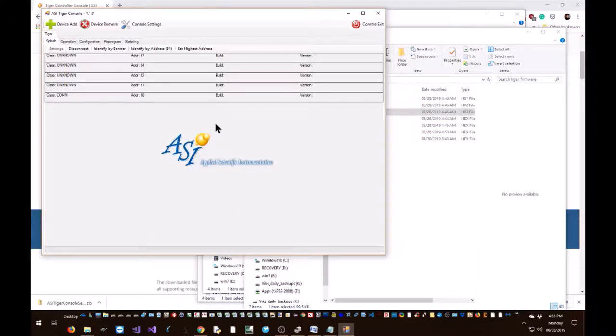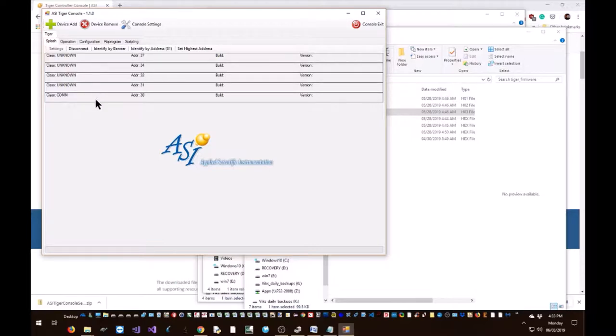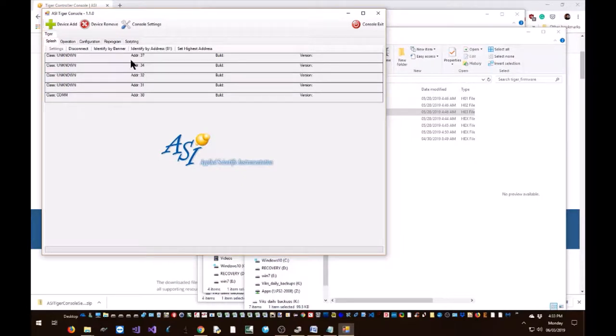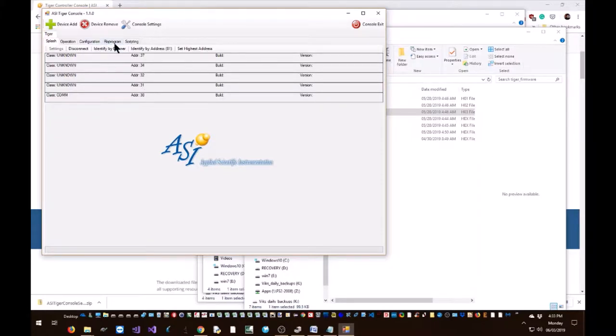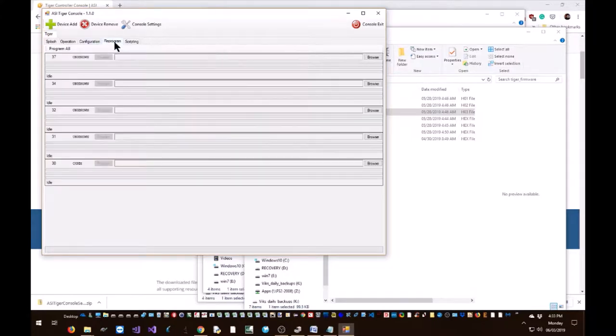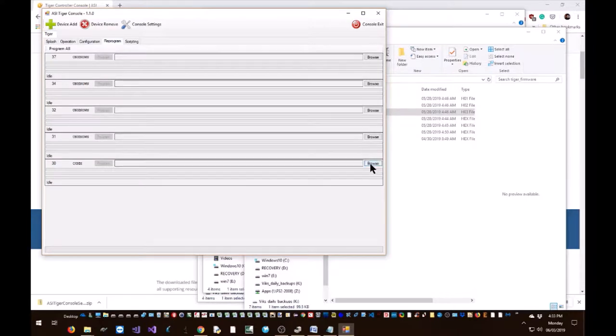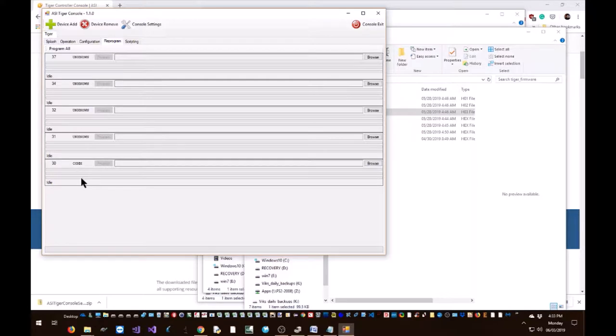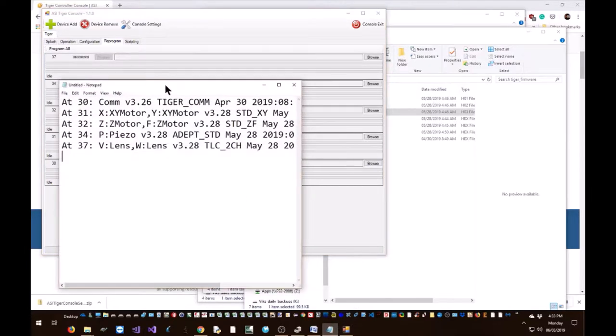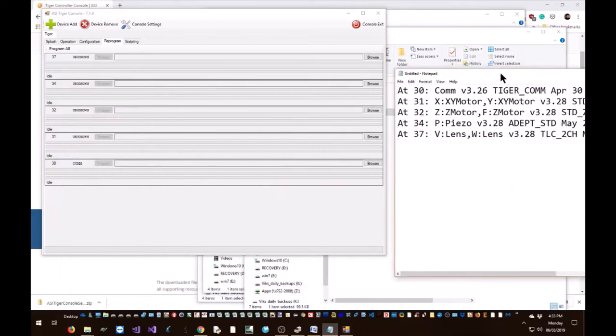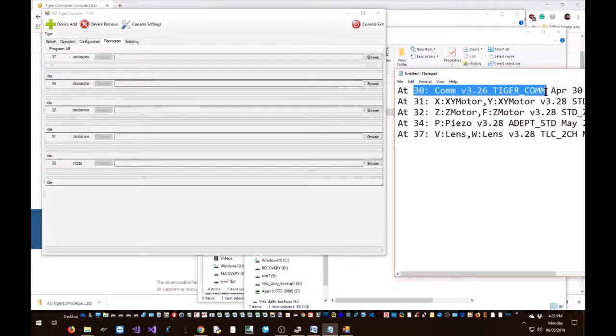Okay, now the COM card has queried all the cards that are present in the box and generated this list. Our controller has five cards in it, and here's the list of five cards, and I think it has found all the cards. So it has successfully found all the cards. Let's go up to the reprogram tab. Now use the browse button and specify what firmware each card should get.